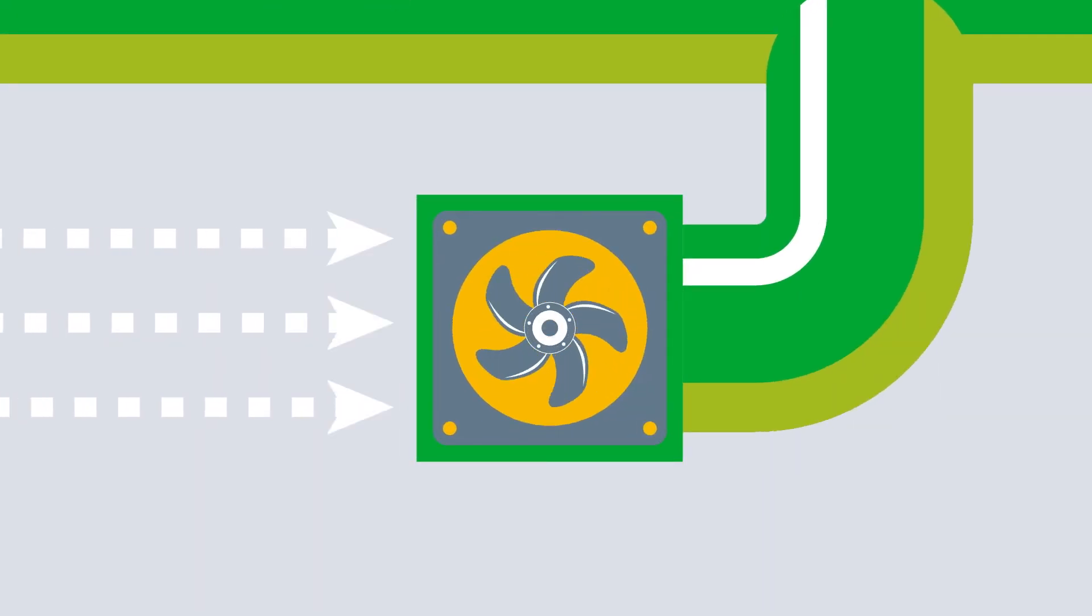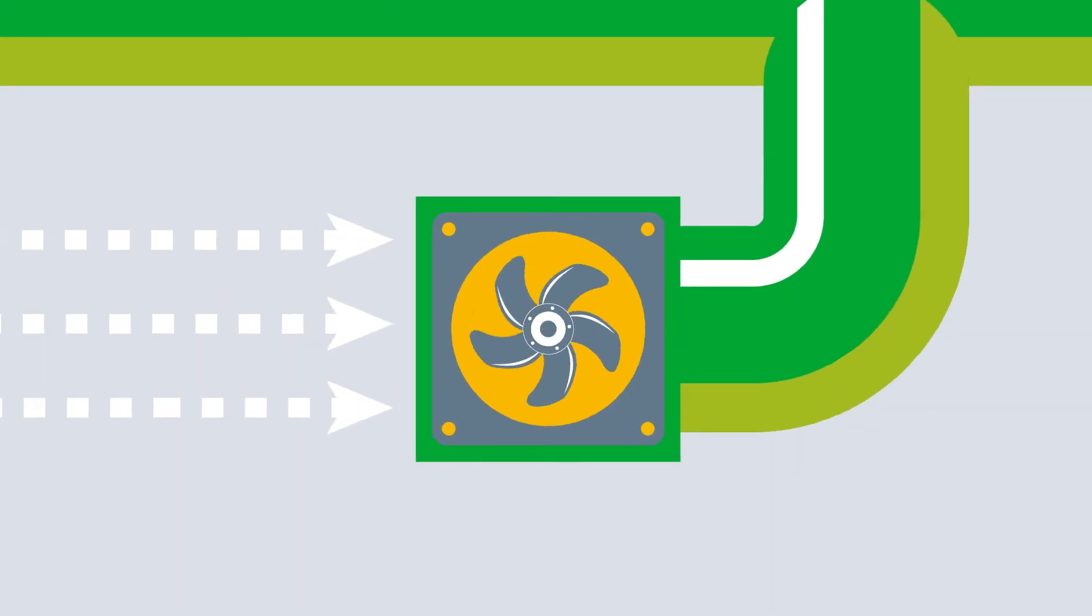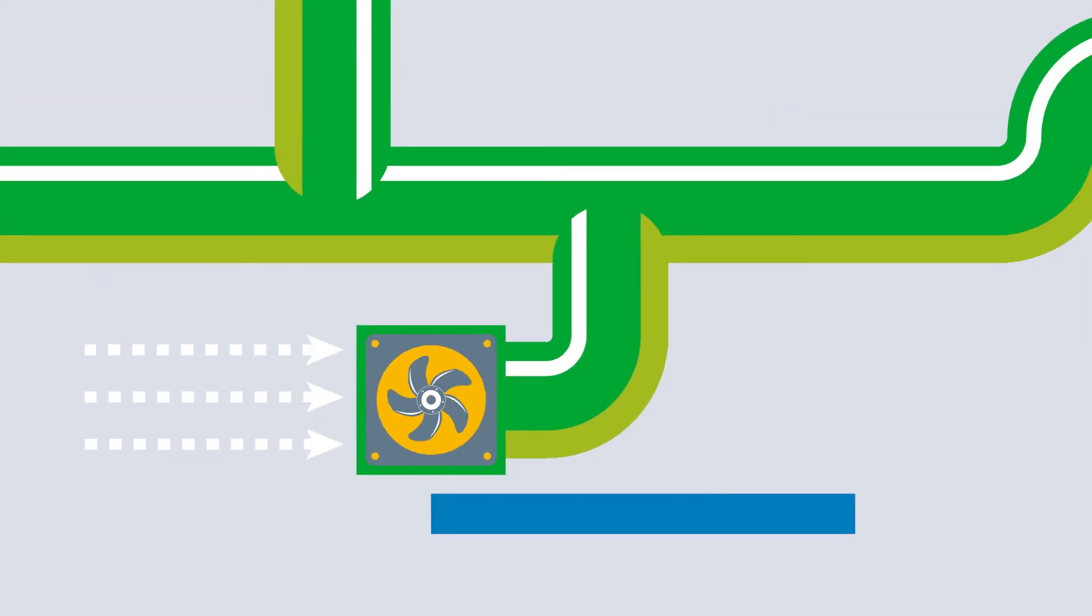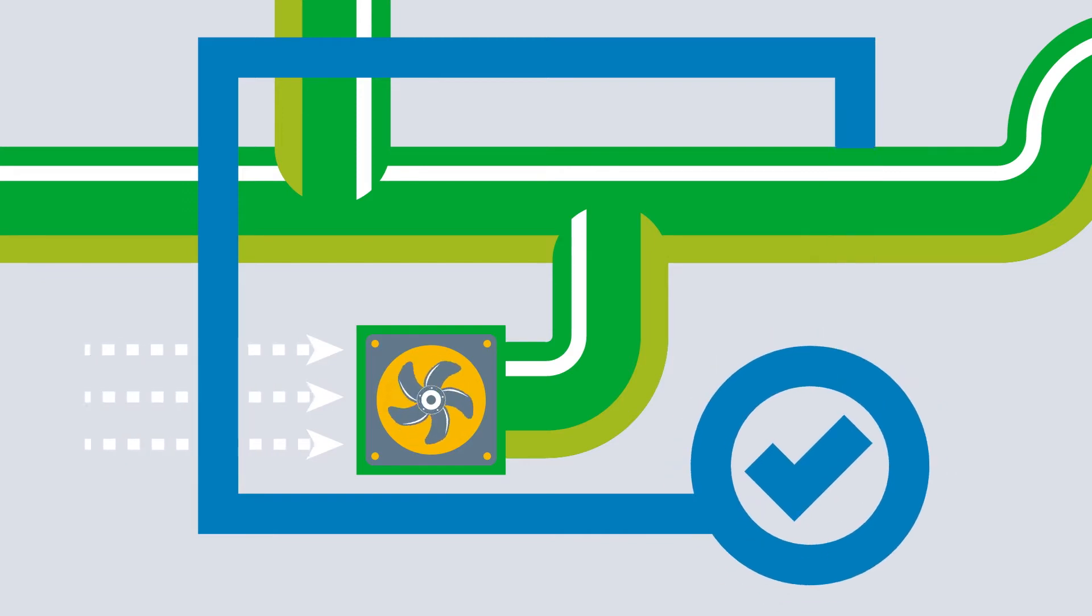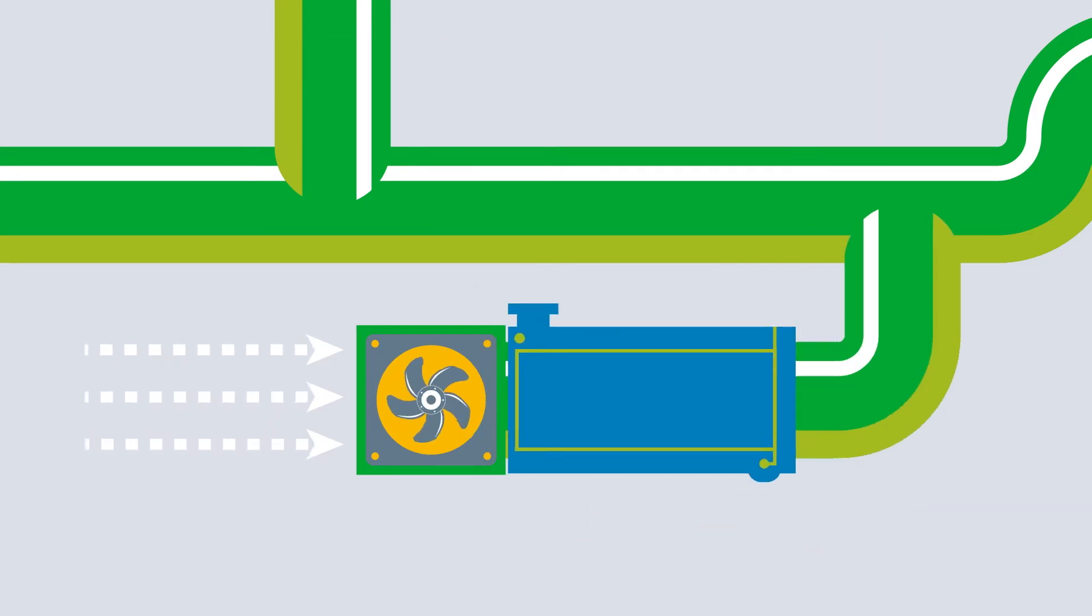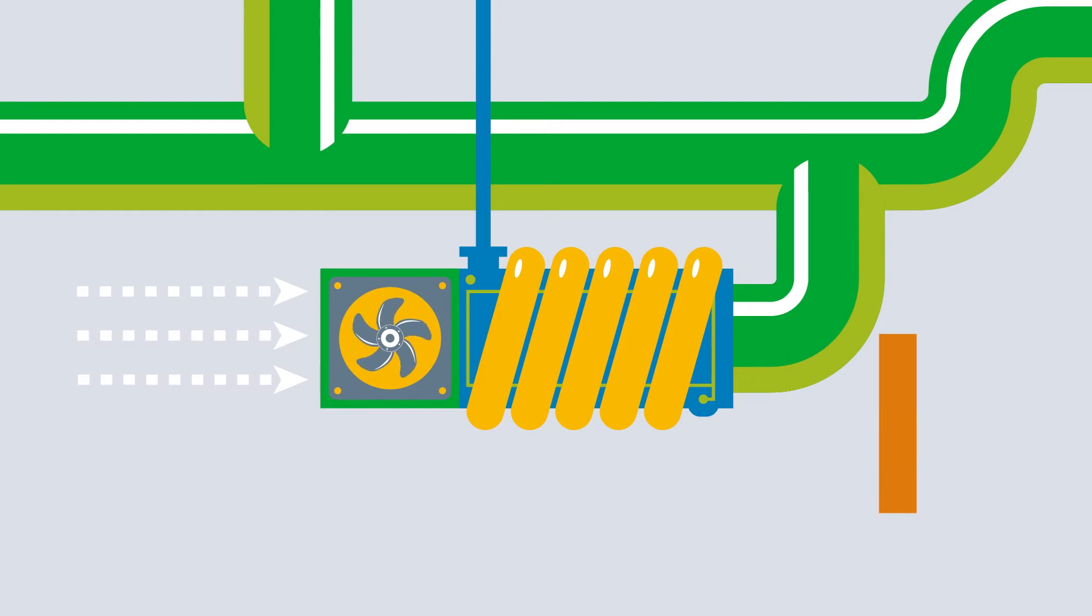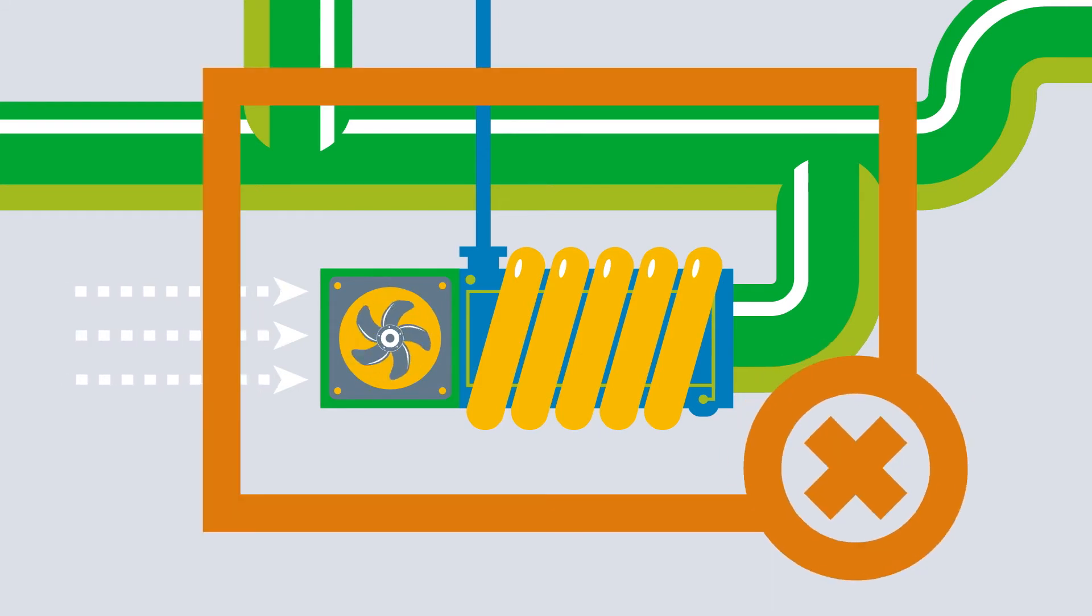Due to their very focused outflow characteristics, axial fans are well suited to direct outflow into a duct network, for example. However, in conjunction with a downstream filter or heat exchanger, this becomes a disadvantage.